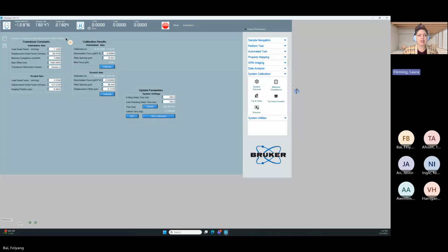So these are the constants. These are set at the factory. When the transducer ships to you, you actually have a physical piece of paper with those numbers on it. If there's any doubt, you can always pull that paper out. If you don't have the paper, you can email me and ask for my records, and I will get them to you. But these look like the correct numbers for this transducer. Sounds like you're checking. Good. Yeah, I'm checking where that paper is. Specifically, we're looking at the load scale factor of 1.12 and the displacement scale factor of 20.8108.